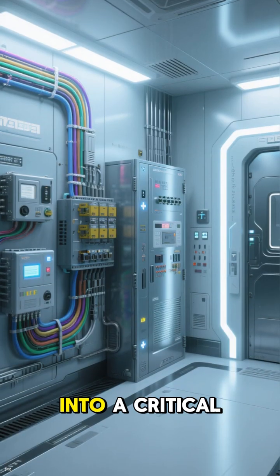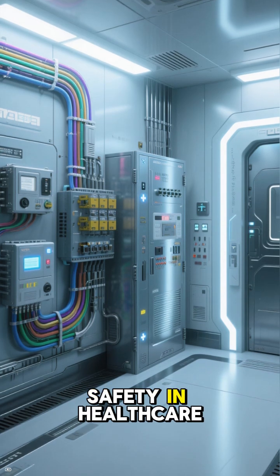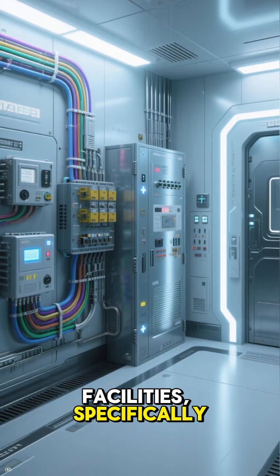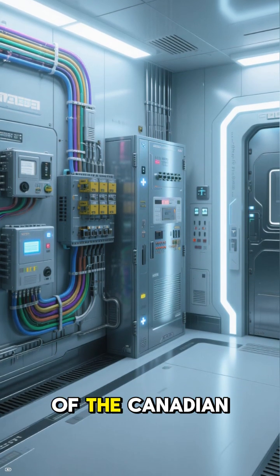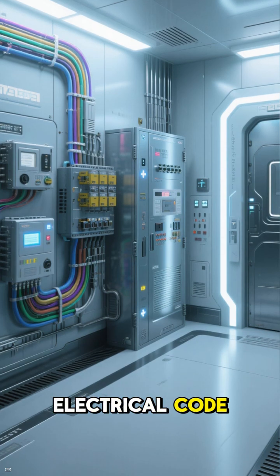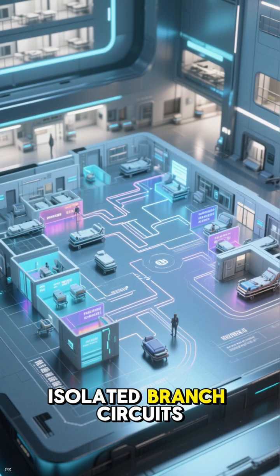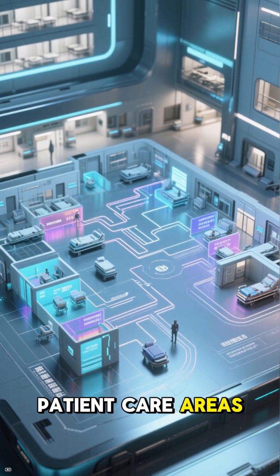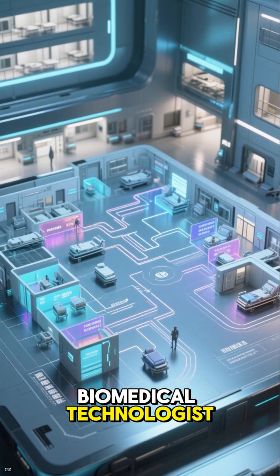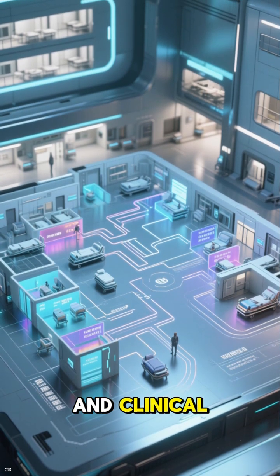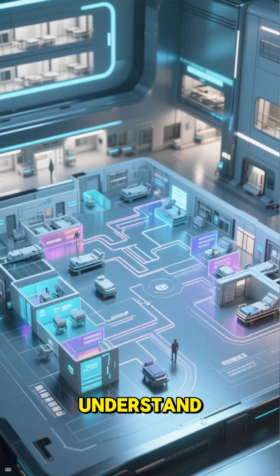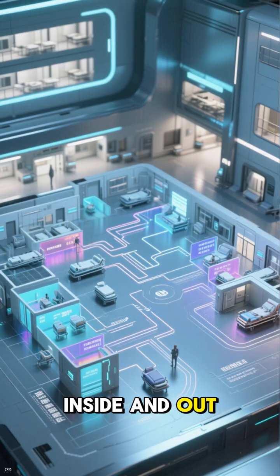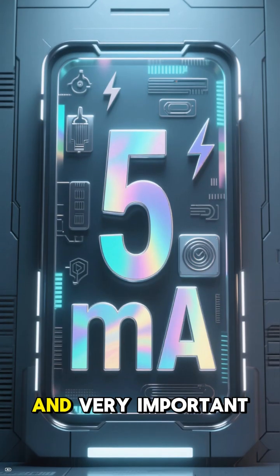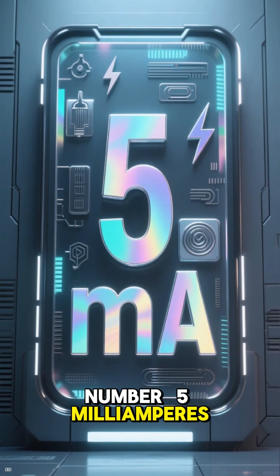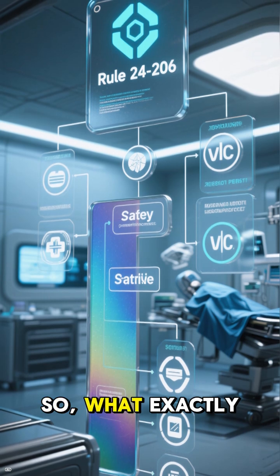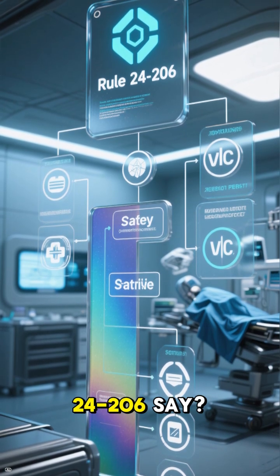Today we're diving deep into a critical aspect of electrical safety in healthcare facilities, specifically Rule 24206 of the Canadian Electrical Code. This rule is all about isolated branch circuits in patient care areas, and it's something every biomedical technologist, hospital electrician, and clinical engineer needs to understand inside and out. We'll be focusing on a very specific and very important number, 5 milliamperes. So, what exactly does Rule 24206 say?